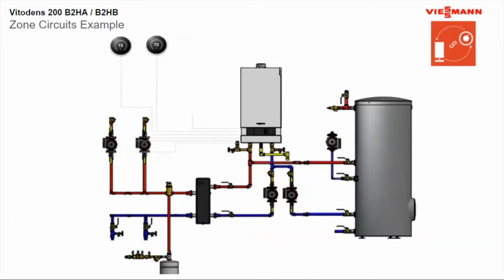So like I was saying, you could either run your thermostats directly to the boiler and have our boiler control your pumps. So in this case here, we have 2 thermostats going over to the boiler, and we're controlling the 2 pumps going to the systems, as well as we're doing our boiler pump, as well as we're doing our domestic pump.